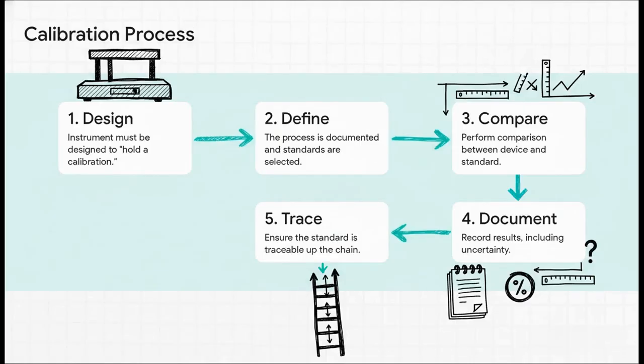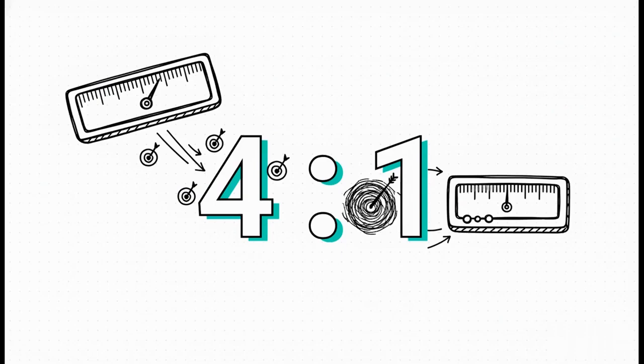So the actual process from start to finish kind of looks like this. It all starts with designing an instrument that's stable enough to hold its calibration. Then you define the exact process, you do the comparison in a controlled environment, you document everything, especially that uncertainty number, and you make sure the standard you're using is itself traceable all the way up the chain. And here's a cool little insider detail, a rule of thumb in the industry. For a calibration to be considered really valid, the standard you're using should be at least 4 times more accurate than the thing you're testing. This 4-to-1 ratio pretty much guarantees that any tiny uncertainty from your standard is so small it barely affects the final result.